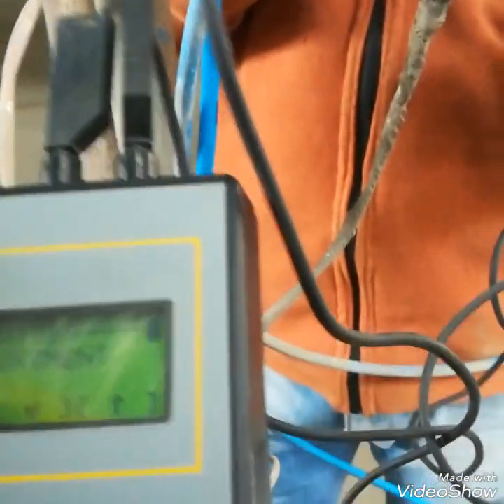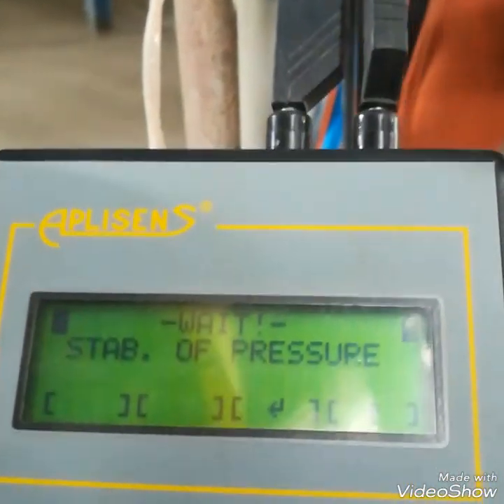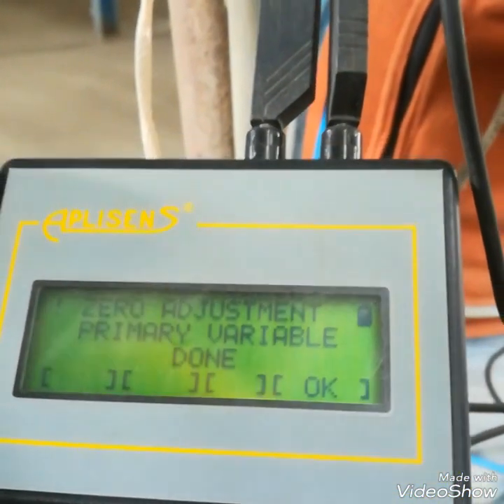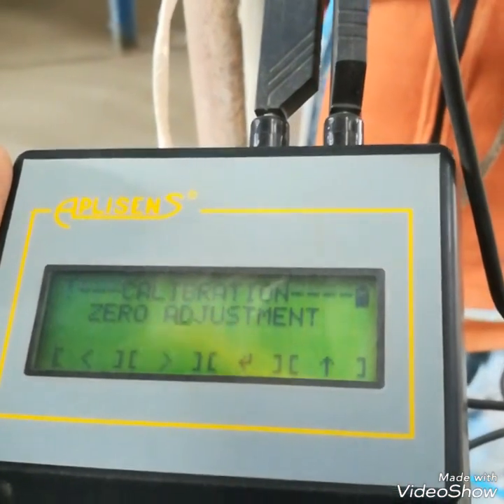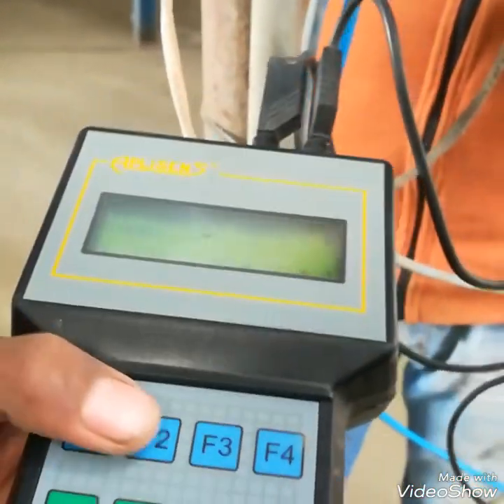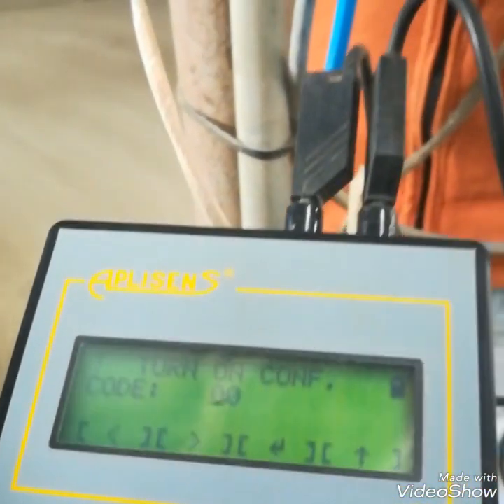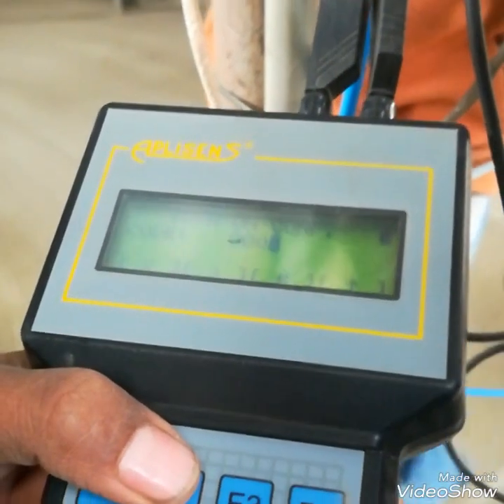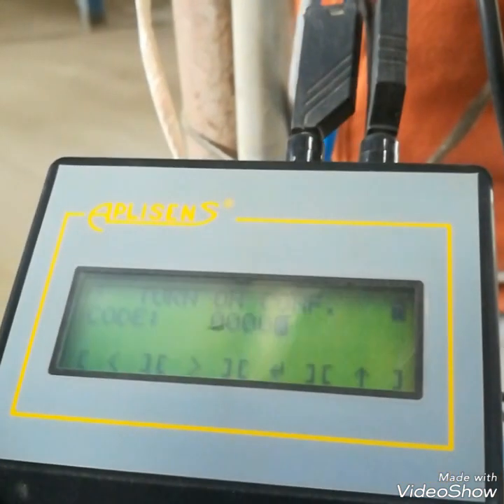After confirming zero — zero adjustment is 0. Now I will give it the pressure for span. In the span, it needs a code: 0 entered 8 times (00000000). I am entering this code for the span calibration.